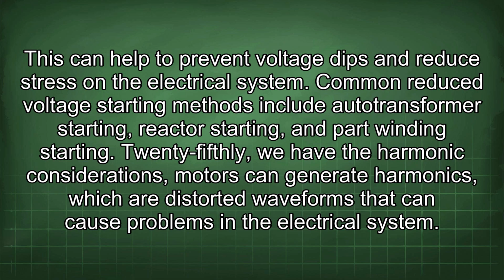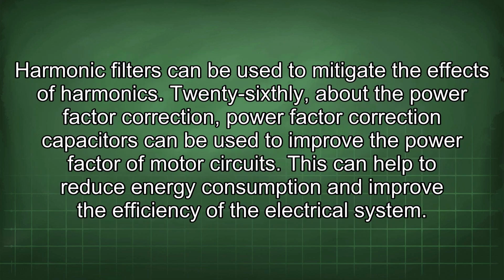Fifthly, we have the harmonic considerations. Motors can generate harmonics, which are distorted waveforms that can cause problems in the electrical system. Harmonic filters can be used to mitigate the effects of harmonics. Sixthly, about the power factor correction. Power factor correction capacitors can be used to improve the power factor of motor circuits. This can help to reduce energy consumption and improve the efficiency of the electrical system.